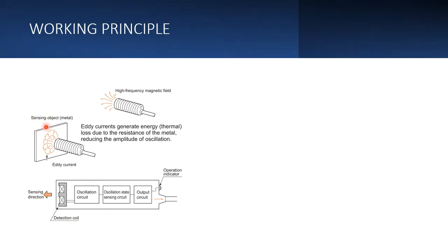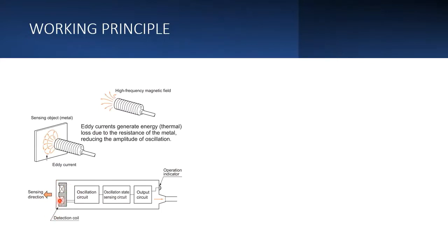The eddy currents get generated in the metal object being sensed. As this object moves away from or closer to the sensor, there are energy losses due to the resistance of the metal, causing a reduction in the amplitude of oscillations. This is sensed by the sensor and it gives a signal. On the back side of the sensor there is a small indicator light — green or red — showing whether a part is in proximity.